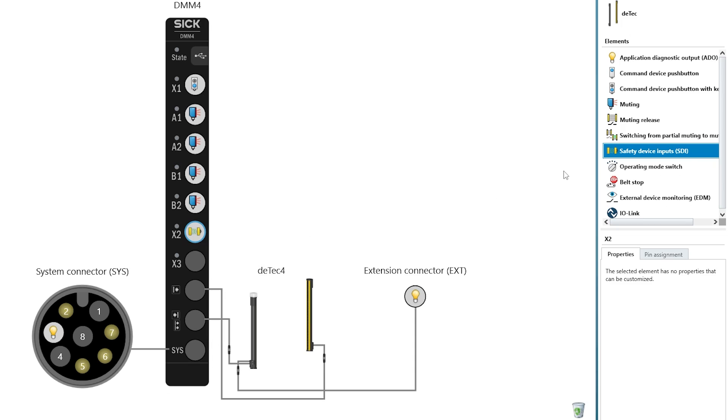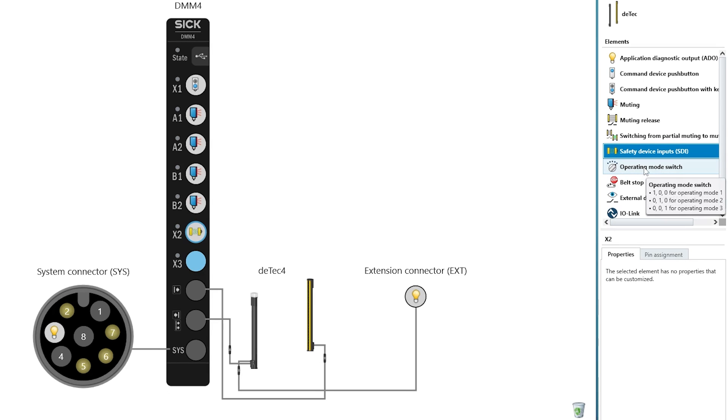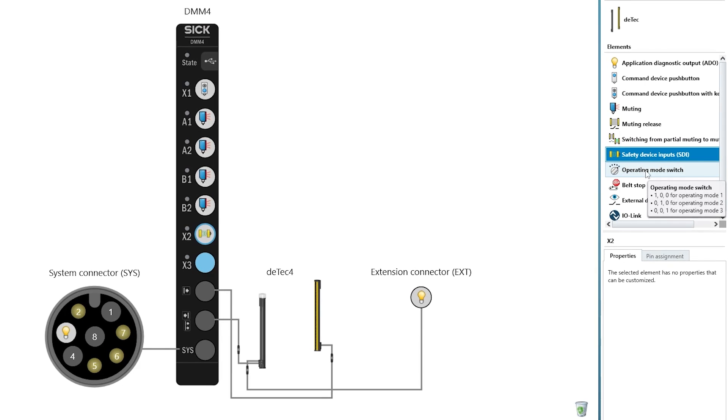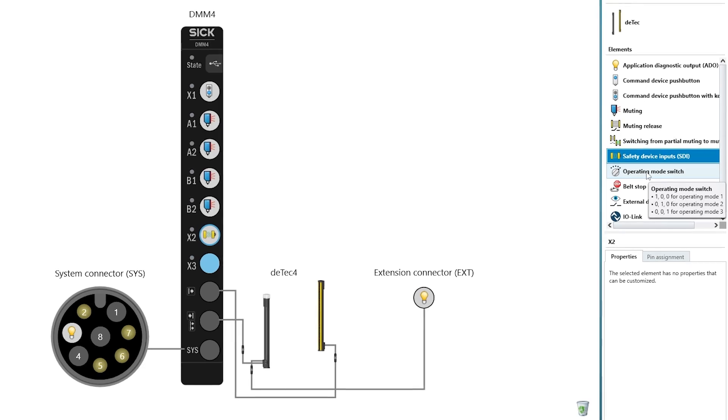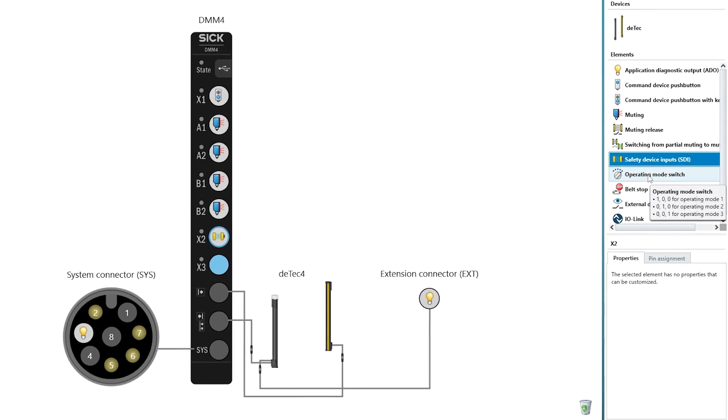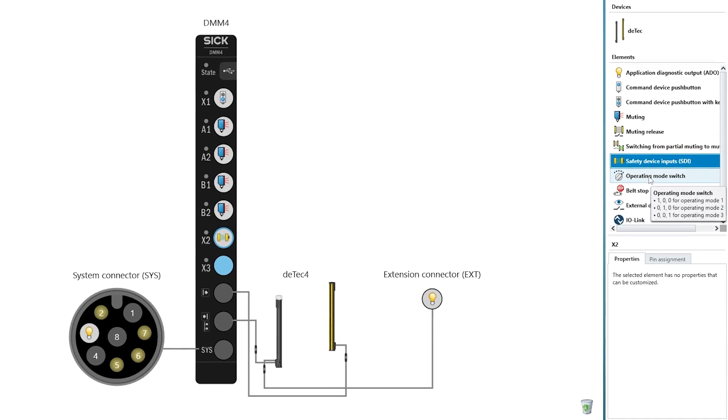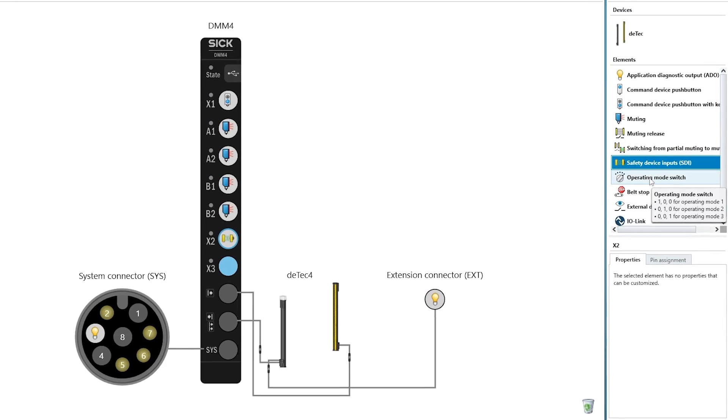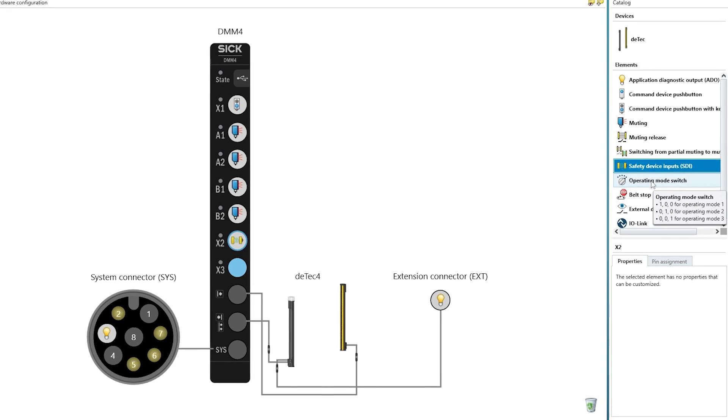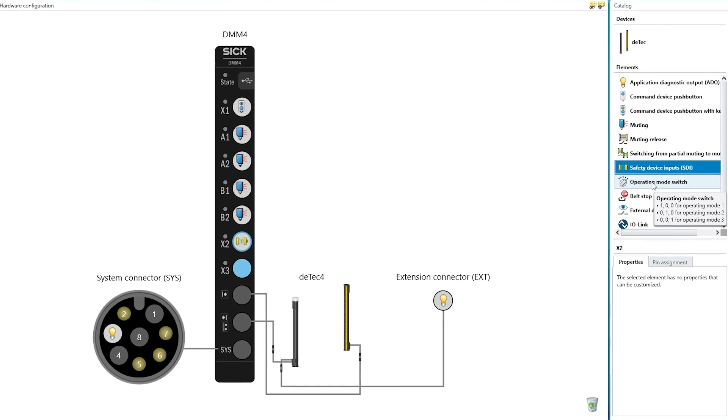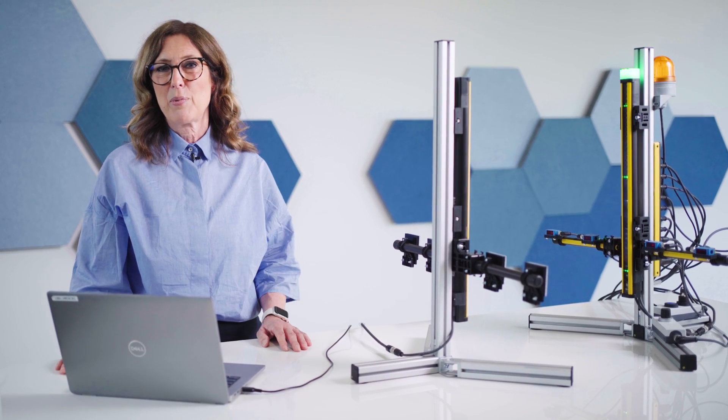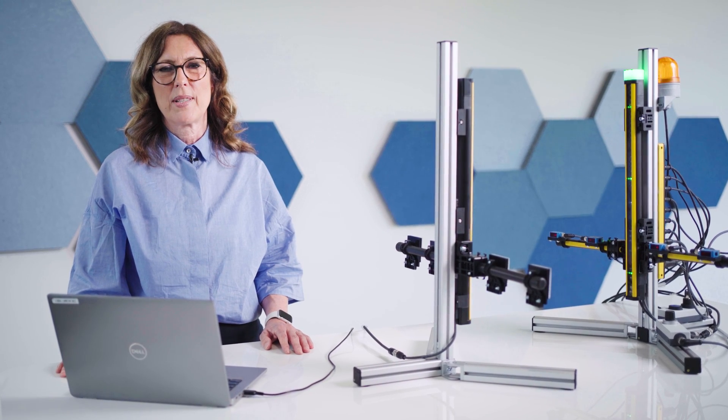If there are different object heights in your application and you want an active protective field above the objects during muting, you can configure up to three different muting operating modes. For switching between different objects, you need an operating mode switch or a signal from the safety controller. Look how easy the hardware configuration was done.